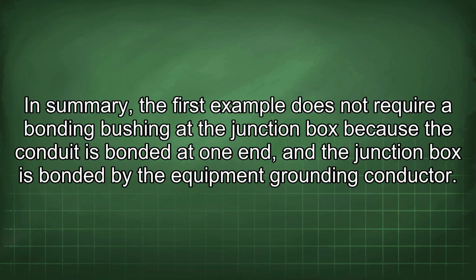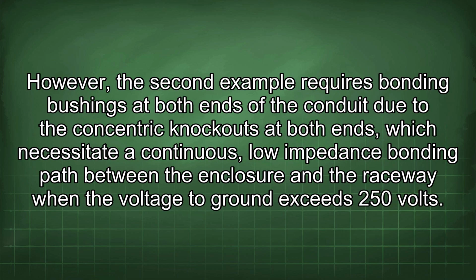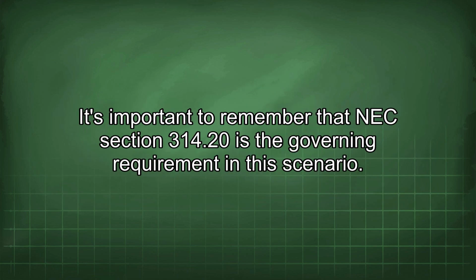In summary, the first example does not require a bonding bushing at the junction box because the conduit is bonded at one end and the junction box is bonded by the equipment grounding conductor. However, the second example requires bonding bushings at both ends of the conduit due to the concentric knockouts at both ends, which necessitate a continuous, low-impedance bonding path between the enclosure and the raceway when the voltage to ground exceeds 250 volts. It's important to remember that NEC section 314.20 is the governing requirement in this scenario.